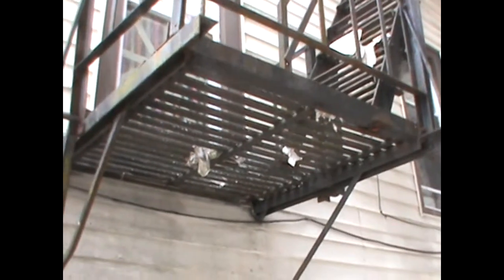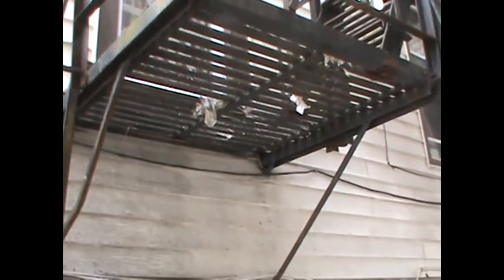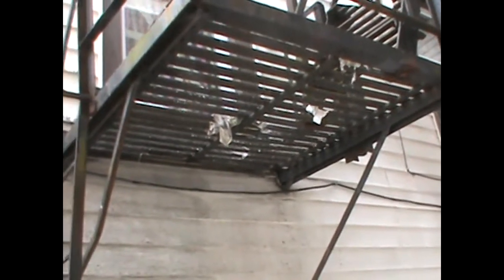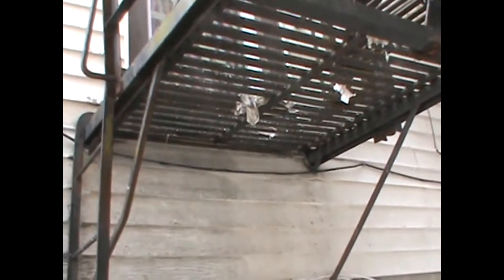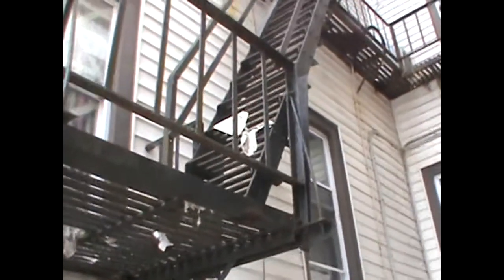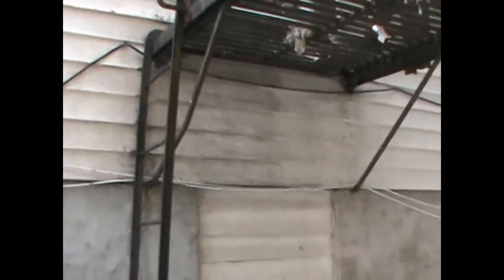So you're about to leave, but you need one more thing to check: the dangerous building code. And that is, do you have anything dangling, anything bent that would make this a dangerous situation while it's getting repaired for the firefighters or the building tenants? Okay, so any dangling or bent supports. Start from the bottom and work your way up. Any bent supports anywhere?